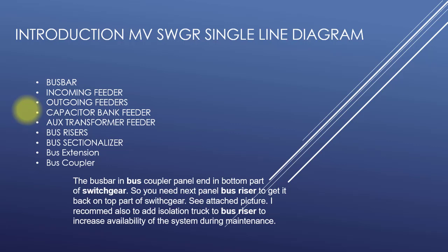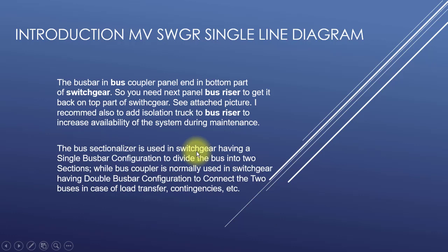There are outgoing feeders feeding the load. In a substation there is also a capacitor bank feeder and auxiliary transformer feeder. Bus risers are used to bring the bus from the bottom part of the switchgear to the top part of the next panel, and it is recommended to add an isolation truck to the bus riser to increase system availability during maintenance. A bus sectionalizer is used when you have a single bus bar and want to divide it into two parts, while a coupler is used in a double bus bar scheme to connect two buses together.